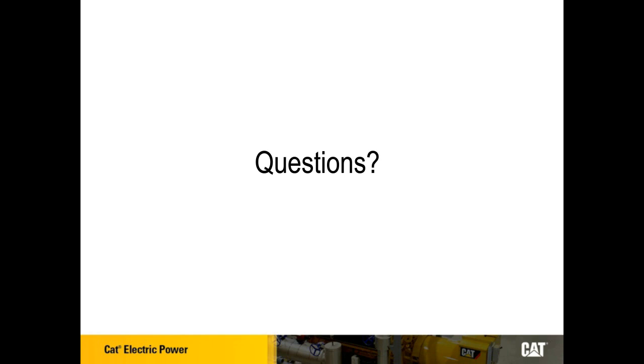Sure, another common question we got. When you get into smaller kW sizes, there's a bit of a breaking point from a dollar-per-kW standpoint where it makes sense to go from gas to diesel or diesel to gas. It's typically in the range where the industry uses more automotive engines, around 150 kW to 200 kW and below. Gas usually makes more sense there. Above that, diesel makes more sense. It's typically right around that automotive derivative engine range, a low cost, since the engines are built in mass quantities at those levels. So the cost breakpoint is certainly around 150 to 200 kW and below.